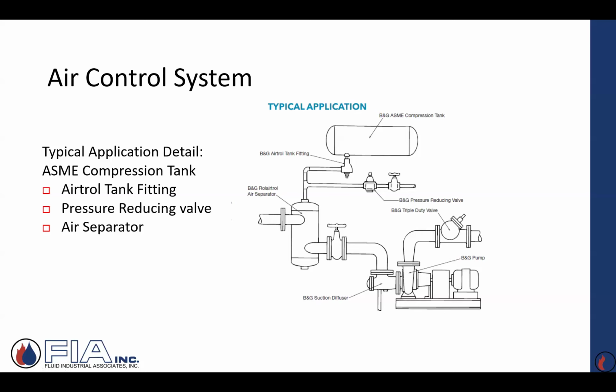Now the boiler shuts down, the system's satisfied, everything starts to cool. Well, as it cools, water can now start to absorb the air. So this air, this nitrogen, is moving in and out of solution as the system heated or cooled. So the whole idea was, because the tank relied on this air as the spring, the cushion, I didn't want to get rid of it. If I vented it, then I'd lose my cushion. And what would happen is the system pressure would drop. And then right over here, you've got this thing called a pressure reducing valve. And he would sense that drop in pressure and he'd add more water. Well, the only place the water would go would be in this tank.